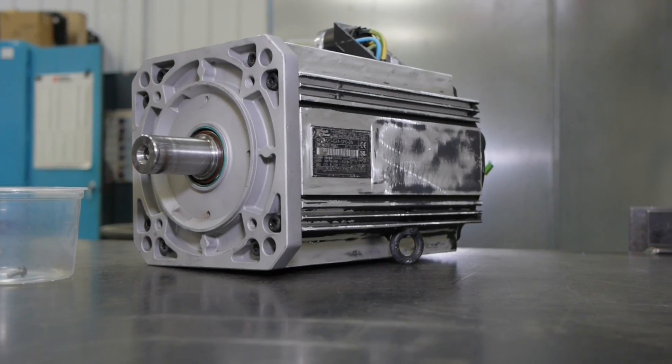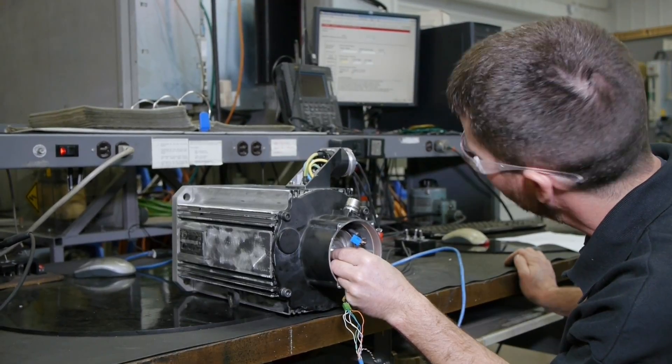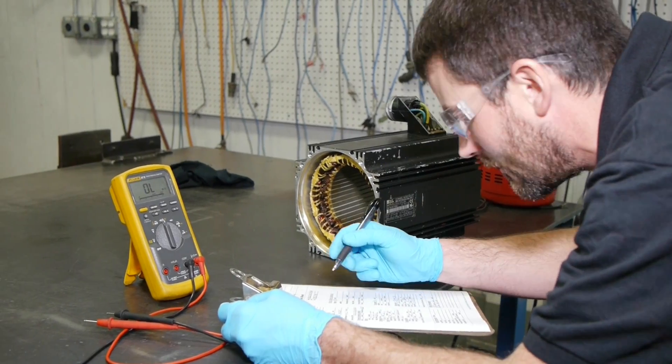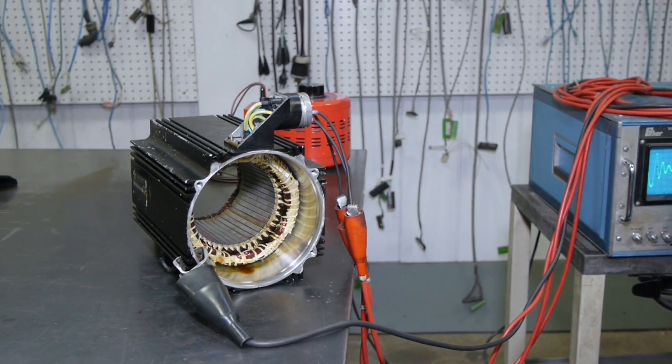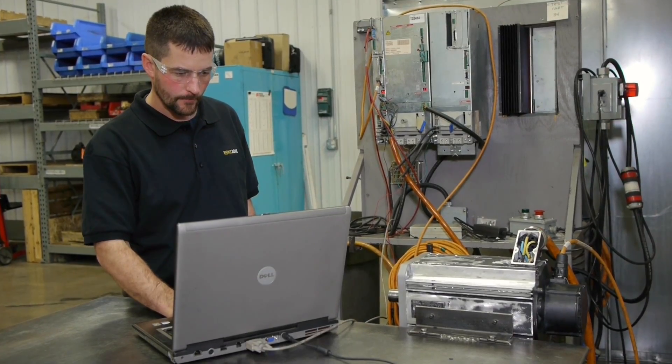Indramat Servo Motor Repair at RepairZone. We use a myriad of electrical and mechanical testing during our thorough evaluation process, including surge testing, back EMF, megger, torque testing of any brakes, mechanical tolerance checks, and verification of feedback devices.